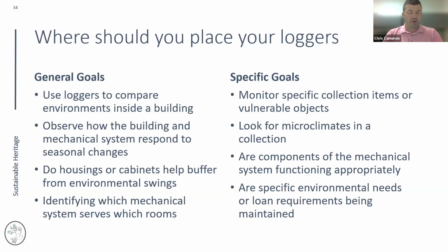You can look for microclimates if you have issues around windows. We've seen loggers put there. As a general condition, if you only get one logger, you want to keep it roughly in the center of a room, about 3 to 6 feet up off the floor, about chest to eye level. But again, use your judgment when you're putting those loggers in. What works best for you and what are you looking for at your institution?